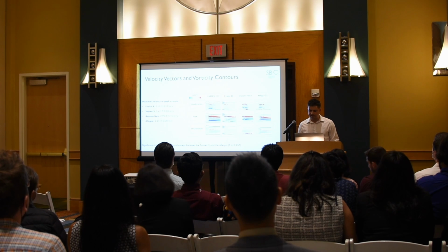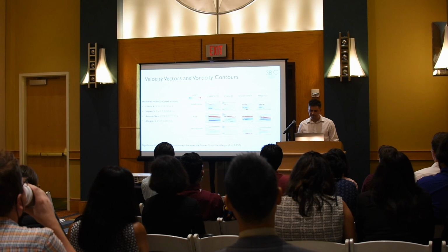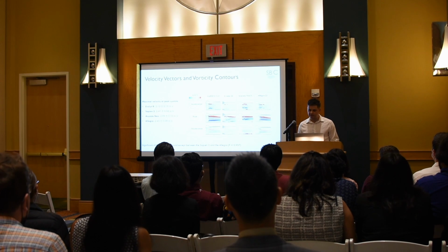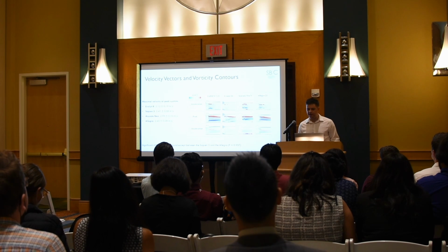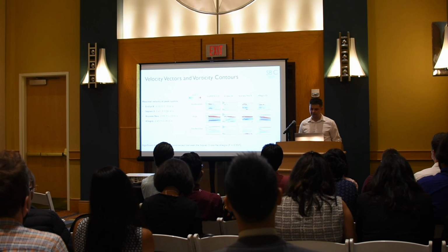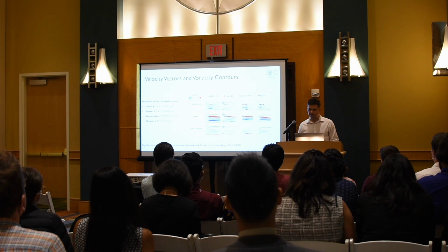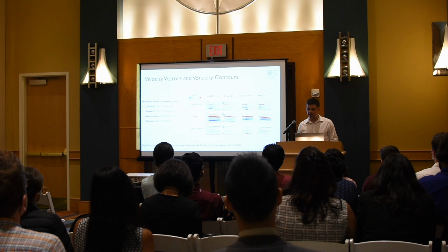As the flow accelerates and reaches the tip of the fully open valve leaflet, it separates from the leaflet tips and travels as a free shear layer, that is, a region of concentrated vorticity as an indicator of flow rotation. Comparing each valve, significant differences were found, except between the Sapien 3 and Allegra.